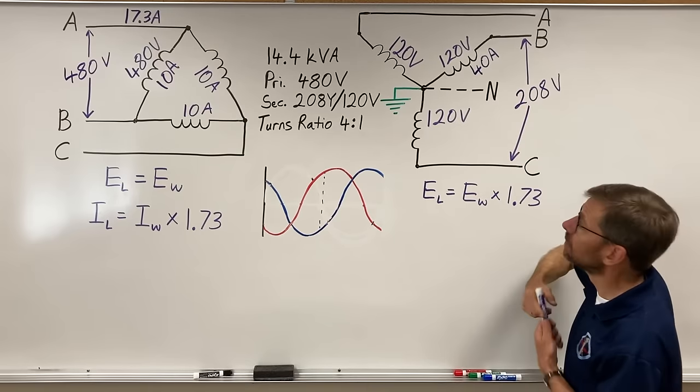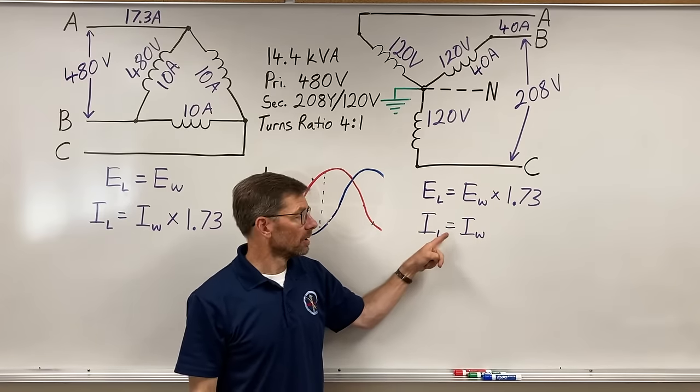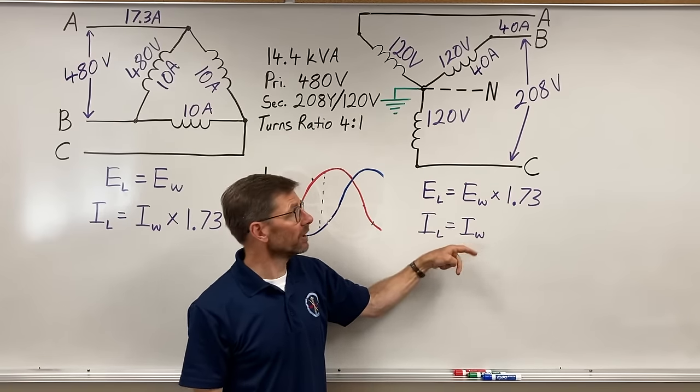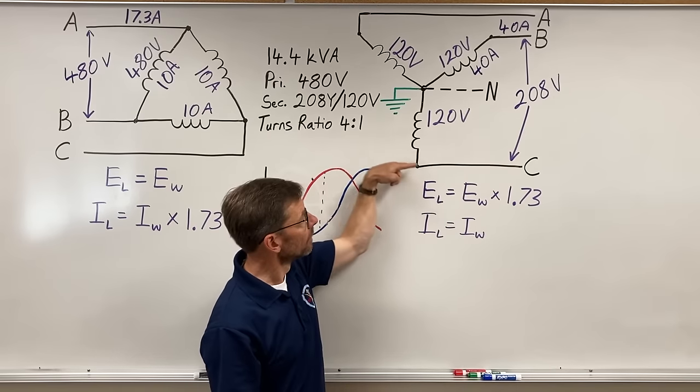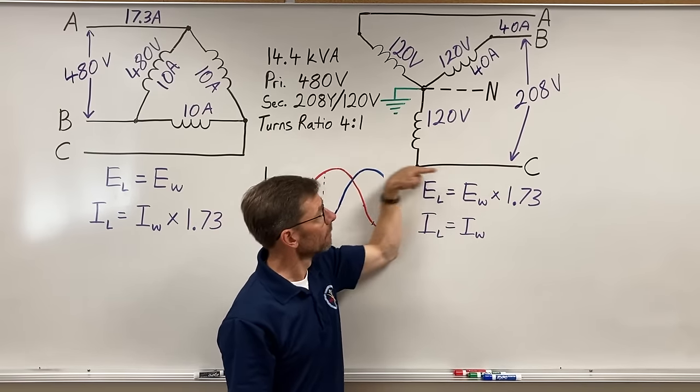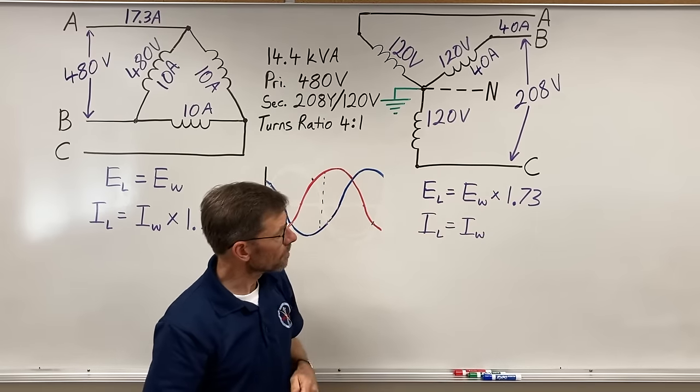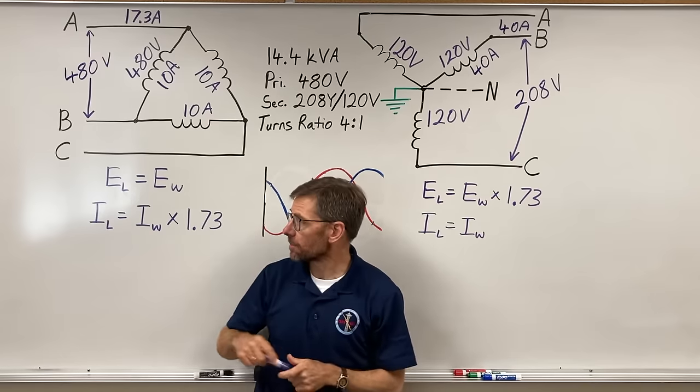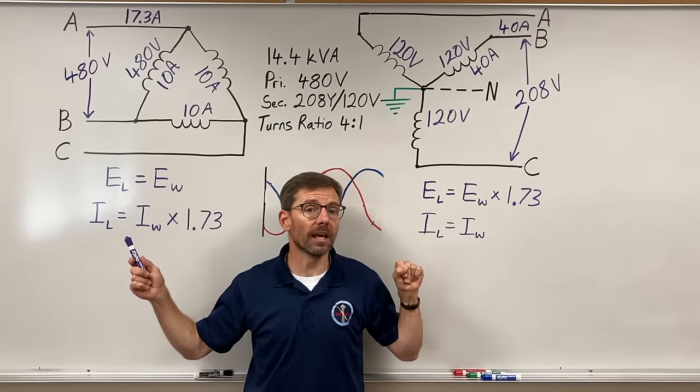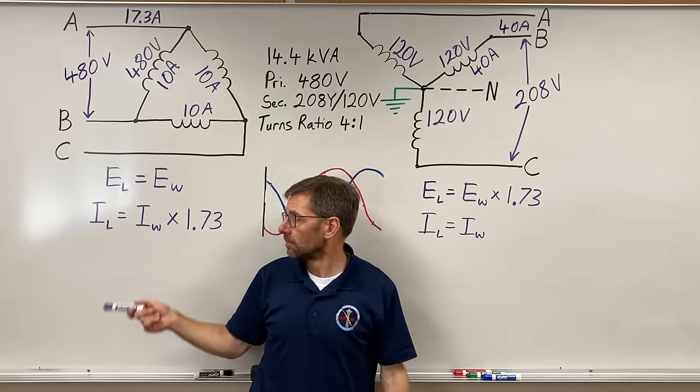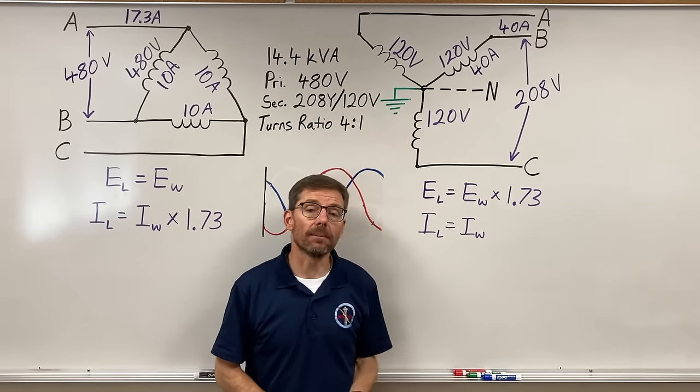So in the Y system, my line current equals my winding current. Whatever amps go through this winding, got to go down this line or back again. AC current flows both directions. So here are our relationships. Voltages are the same in delta. Different between the line and winding in a Y system. Amperages, line to winding, different in a delta. The same in a Y.